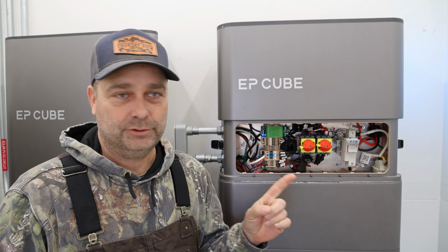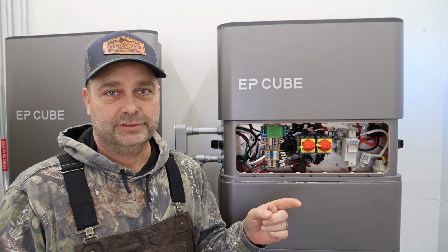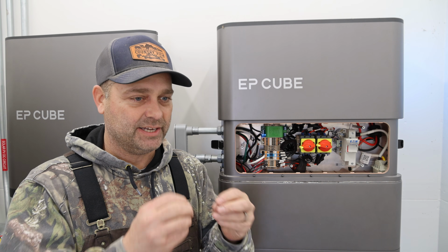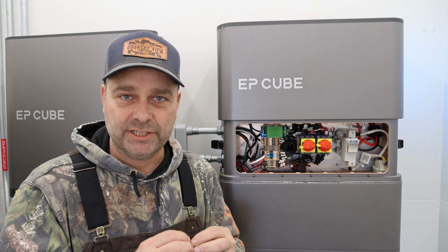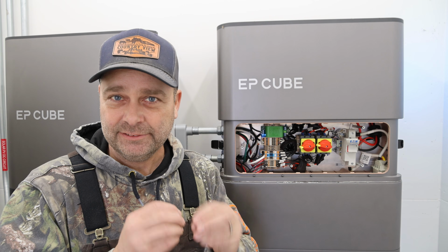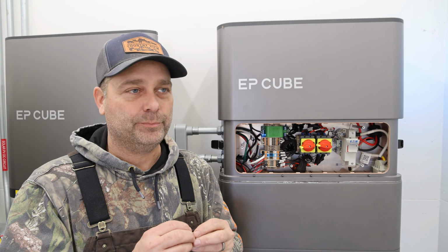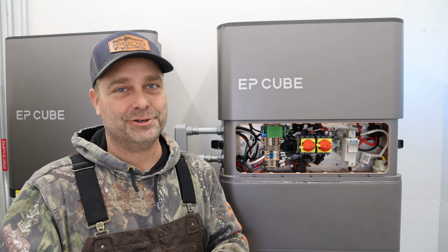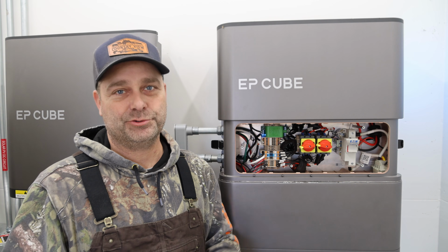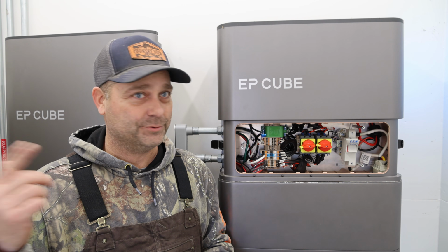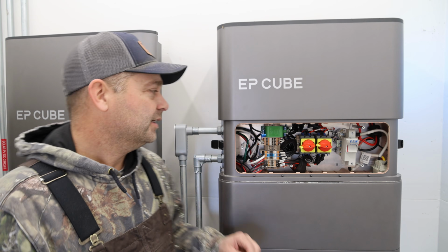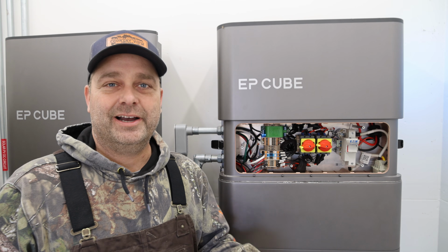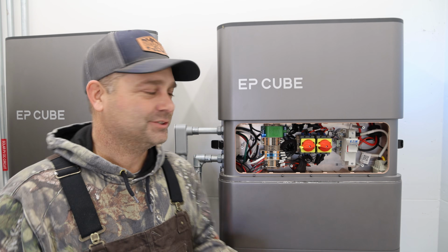Now the error I was getting was an arc fault detection. Anytime you have rooftop solar, you have to have arc fault detection because it detects if there is a loose connection and it's sizzling, or arcing, and that produces heat, which could in turn turn into a fire. That's why it's required when you have solar panels on a building or structure. So first thing in my mind is I've got a problem with my solar panels.